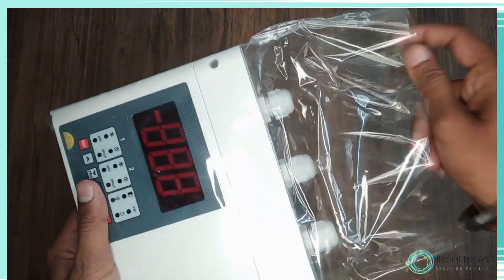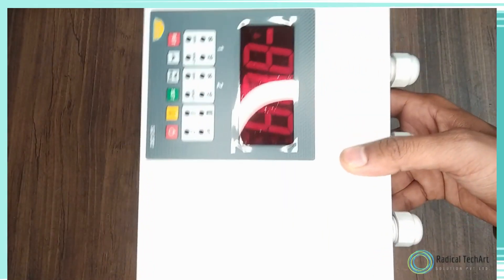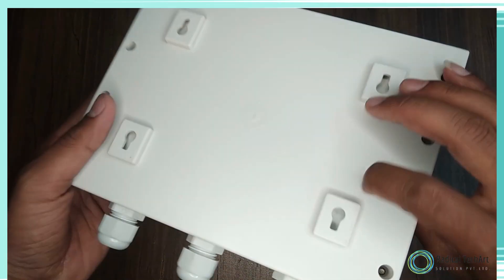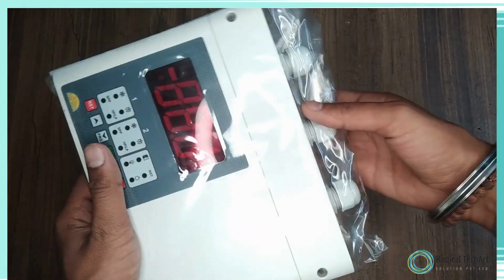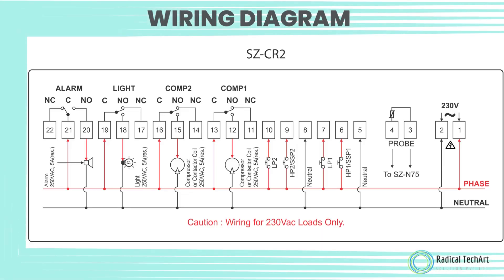The SZ-CR2 is a two-compressor controller with separate setpoints and differentials for each compressor. They are specifically designed for refrigeration applications wherein the compressor cuts off at its setpoint and is restarted at a temperature of setpoint plus differential. Here is the compressor controller of Sub-Zero brand, and this is the wire diagram of this controller.